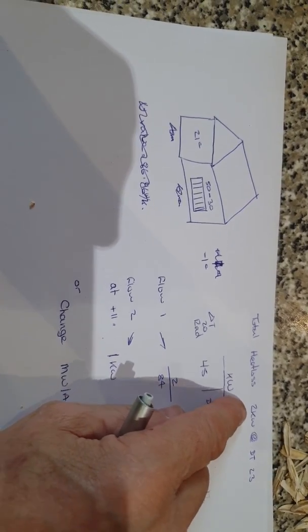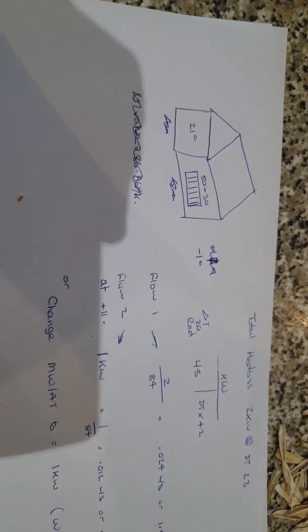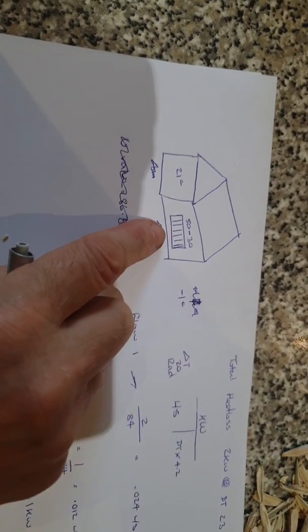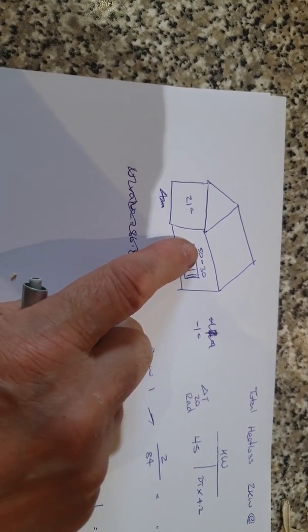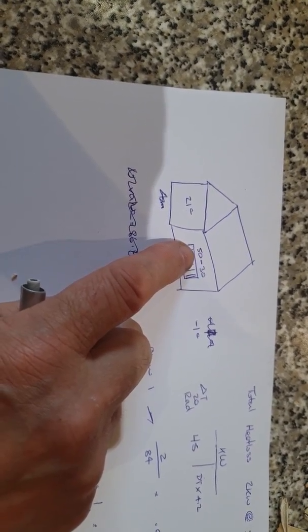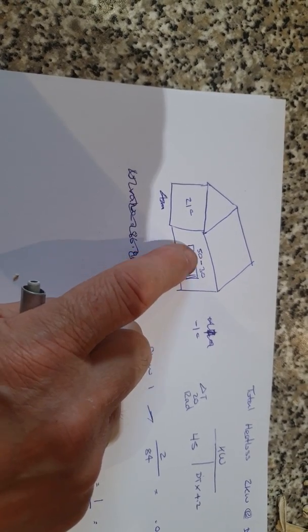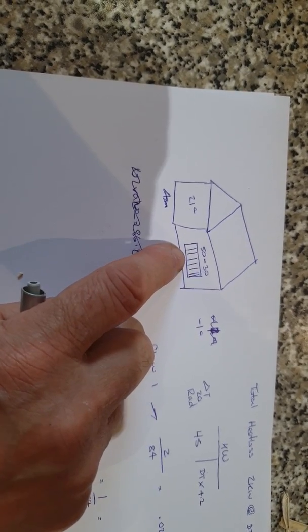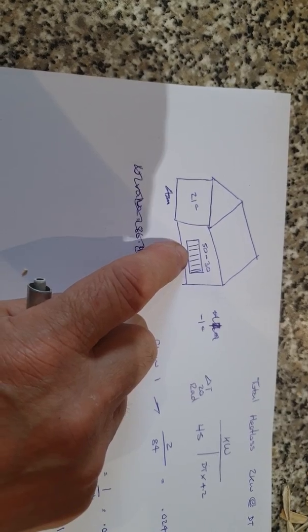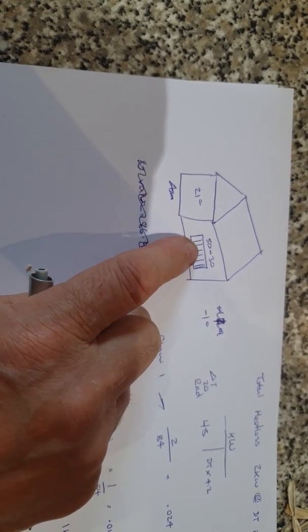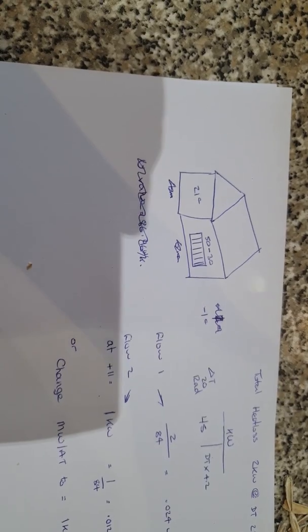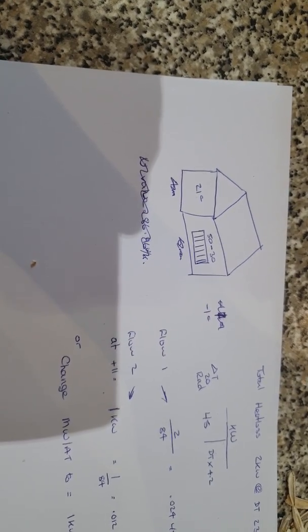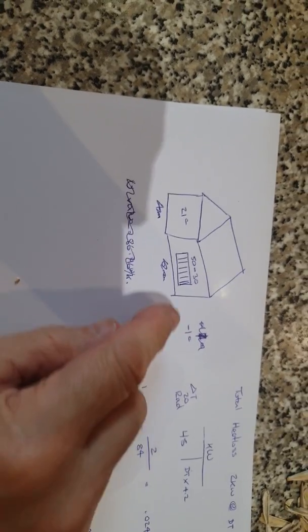For this example, I've decided that we've got 2 kilowatts at that temperature, and this radiator here is sized for 50/30. That's a flow of 50, return of 30, delta T 20 to give us a mean water temperature of 40 to maintain 21 inside when it's minus 1 outside.